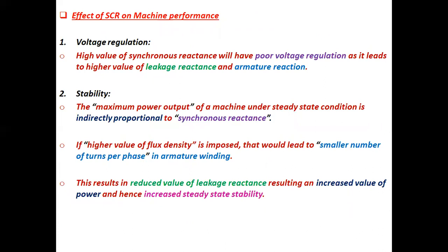Effect of SCR on machine performance. Number 1, voltage regulation. A high value of synchronous reactance will have poor voltage regulation as it leads to a higher value of leakage reactance and armature reaction. Number 2, stability. The maximum power output of a machine under steady state condition is inversely proportional to synchronous reactance.